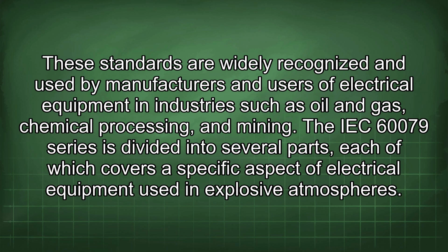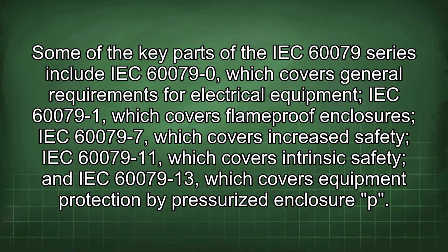in explosive atmospheres. Some of the key parts of the IEC 60079 series include IEC 60079-0, which covers general requirements for electrical equipment, IEC 60079-1, which covers flameproof enclosures, IEC 60079-7, which covers increased safety, IEC 60079-11, which covers intrinsic safety, and IEC 60079-13, which covers equipment protection by pressurized enclosure.